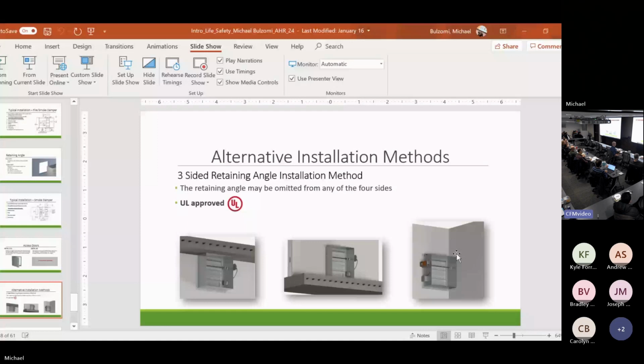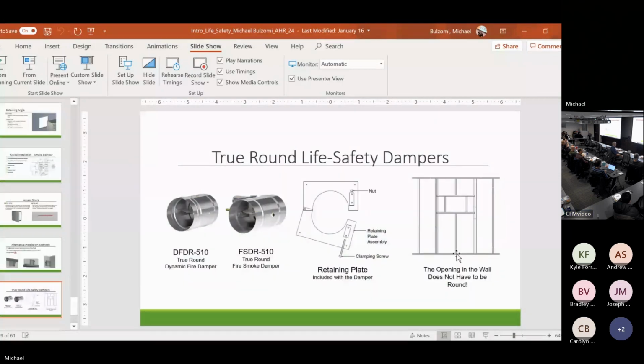You have to have a UL approved installation to do a 3-sided angle installation. So if you go working with a company that isn't Greenheck, and the contractor has an issue, hey, my damper is tight to the wall, I can only get the angle on 3 sides, just request a copy of the UL approved 3-sided angle installation and make sure they have that installation. That's all you got to do.